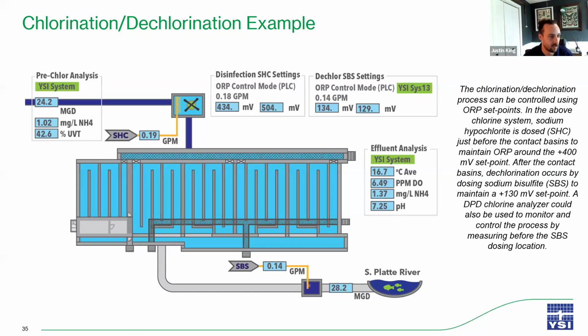So we can either do this by adding a few analyzers into these contact basins and right at the effluent. Depending, you could do a feedback or a feed forward system, where you're either checking the dosage at the middle of the contact basins and feeding back to the chemical doser, letting the doser know if it needs to dose more or less based off of a desired residual. Or you could do a feed forward where you are measuring different parameters in the water right before dosing and seeing the amount of chlorine residual that would be needed to effectively chlorinate the water.